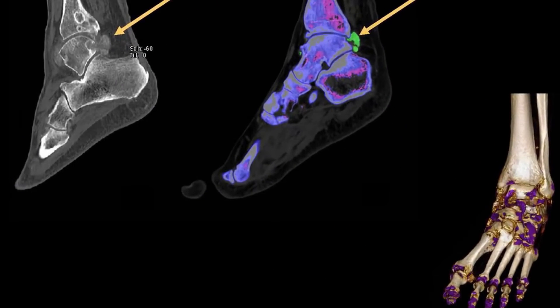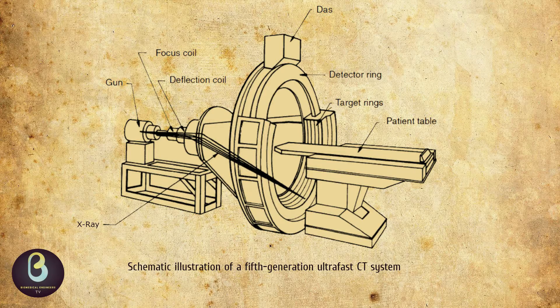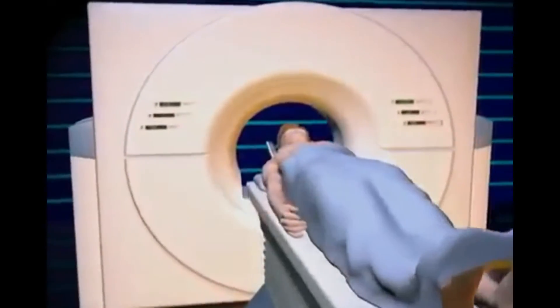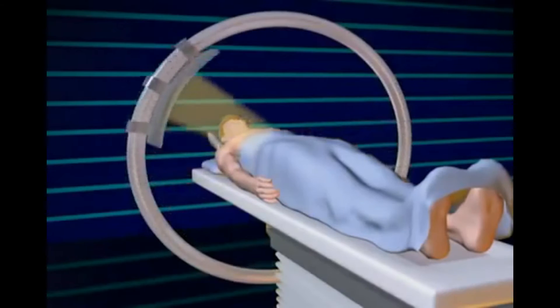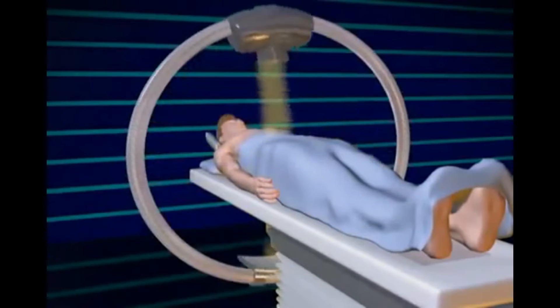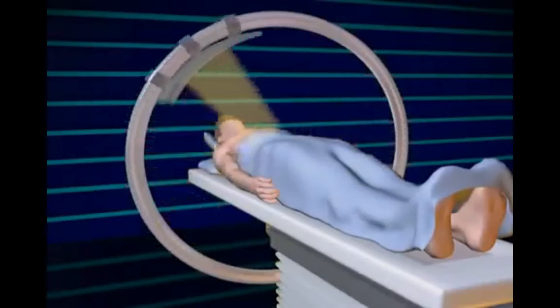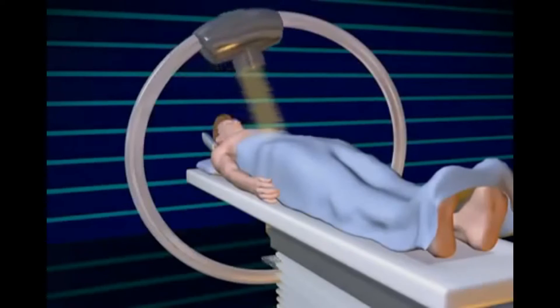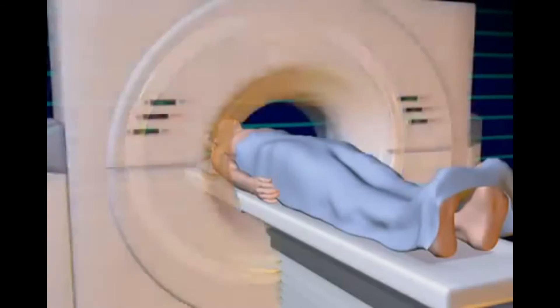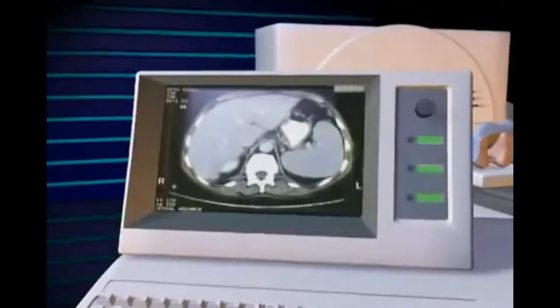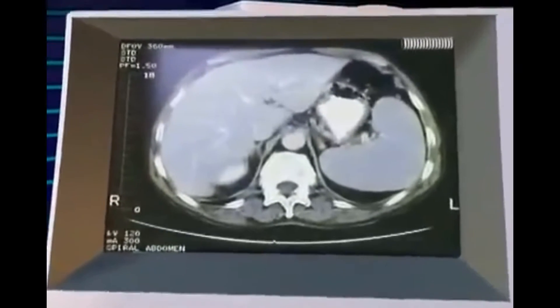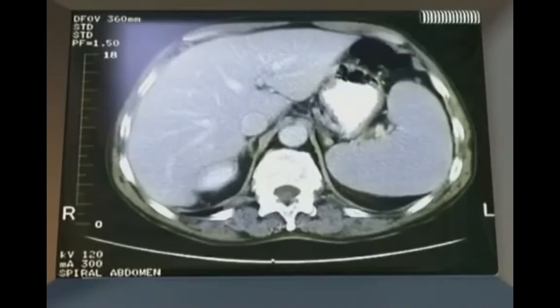There are basically two processes of absorption: the photoelectric effect and the Compton effect. This phenomenon is represented by a single coefficient. In the particular case of CT, the emitter of X-rays rotates around the patient and the detectors, placed in diametrically opposite sides, pick up the images of a body section. Beam and detector move in synchrony. Unlike X-ray radiography, the detectors of the CT scanner do not produce an image. They measure the transmission of a thin beam, 1 to 10 mm of X-rays, through a full scan of the body. The image of that section is taken from different angles, and this allows retrieval of information on depth in the third dimension.